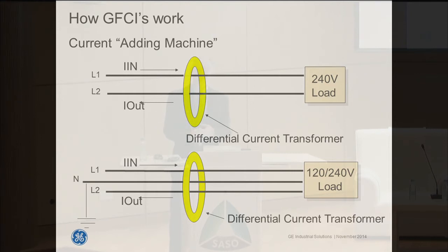These also are used on multi-pole devices, so 240 volt loads, line 1 and line 2 going out to the load, and again measuring that the same amount of current comes back. And in a line 1 and line 2 with a neutral, in a similar manner, they'll measure that the same amount of current is coming back on all 3 conductors. So there are different applications. In addition, there are also equipment protection ground fault devices that are sold through the NEMA devices, and these will sense in multi-phase applications as well, 3-phase.